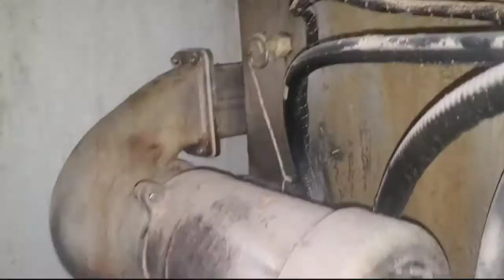Based on that chart, this thing's reading way high. There ain't no way that's reading 110 degrees. Right here, this sensor, it feels about 75 degrees Fahrenheit to me. It ain't no 120, that ain't no sensor.